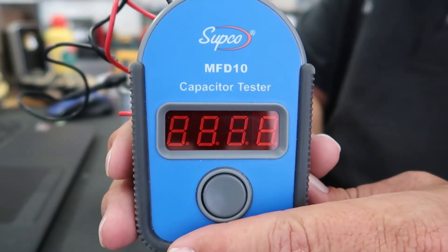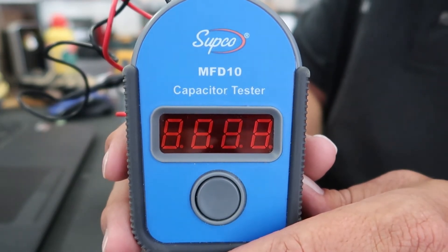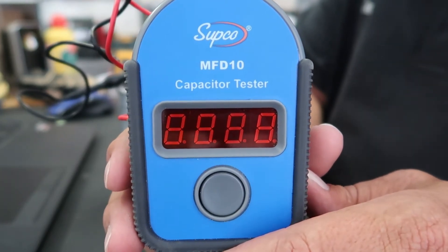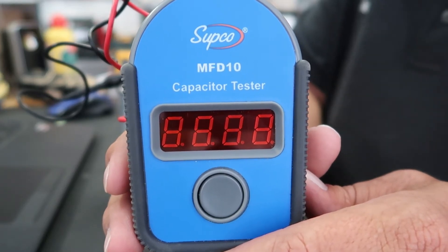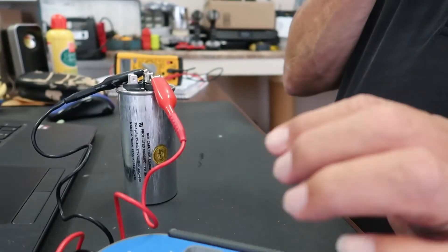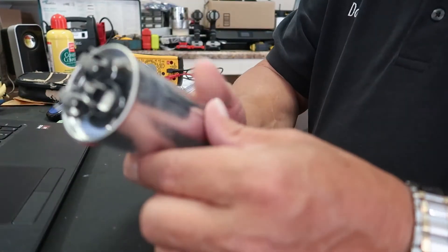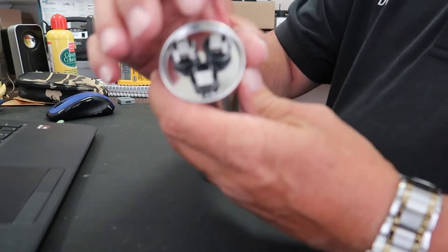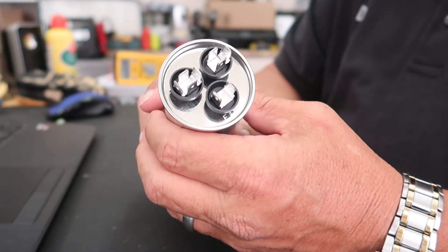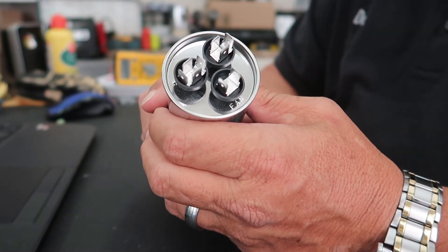Now, if you've got a 35/5 capacitor and your reading is somewhere down around 20 to 25 microfarads, I'm going to say that capacitor should be replaced. If you're testing the fan side and you're getting a 3 or lower, you need to replace that capacitor as well. Also, if you look at your capacitor on your outdoor unit and the top is swollen or bubbled up, that's a pretty good indication it needs to be changed out — it's probably bad, and that could be the main fault of why your unit's not running.